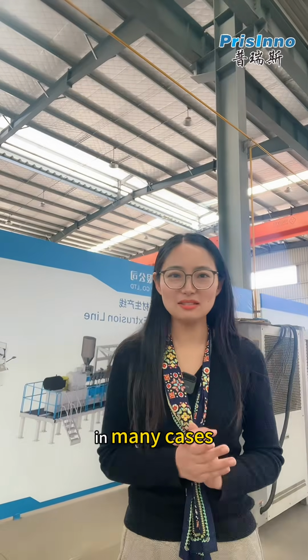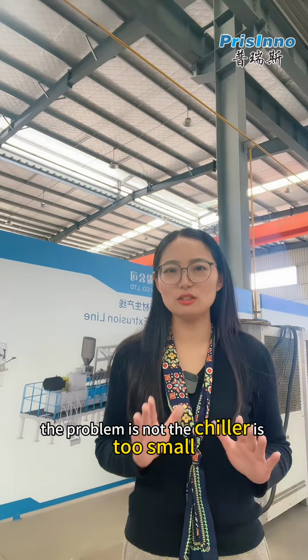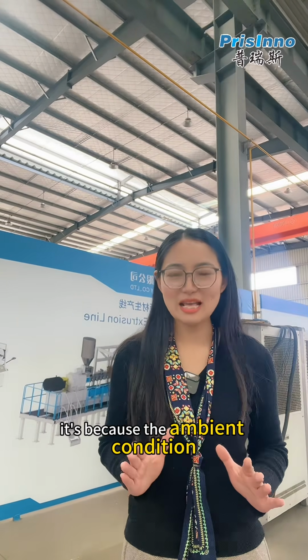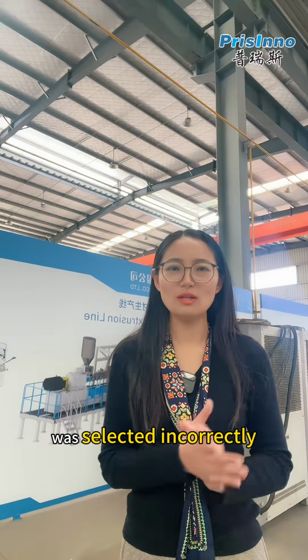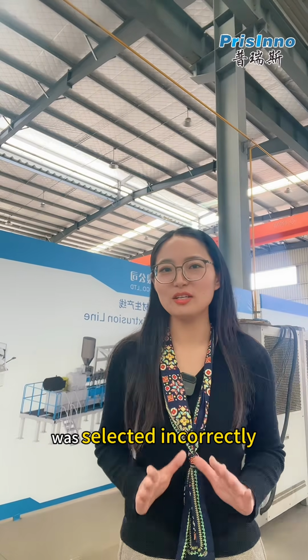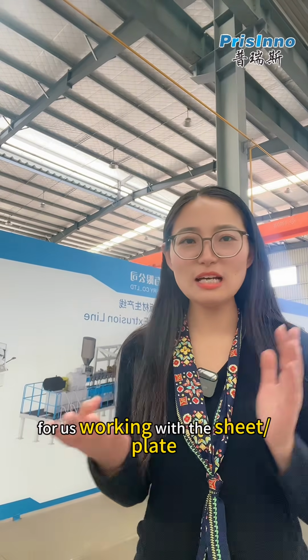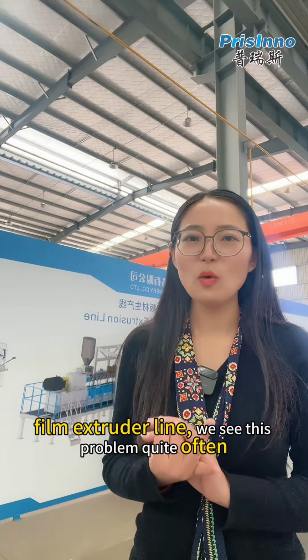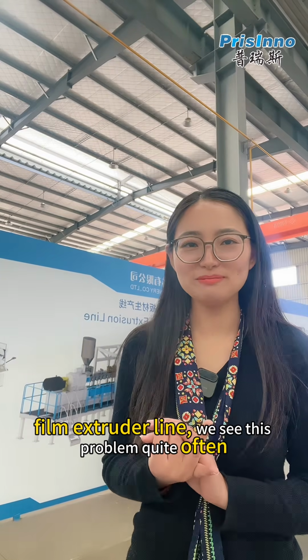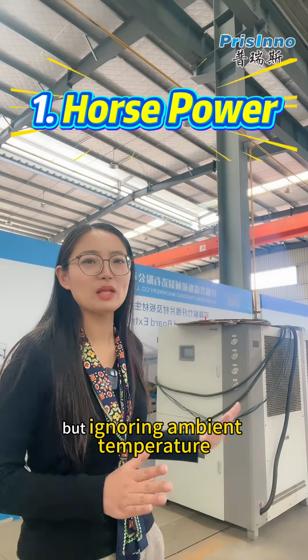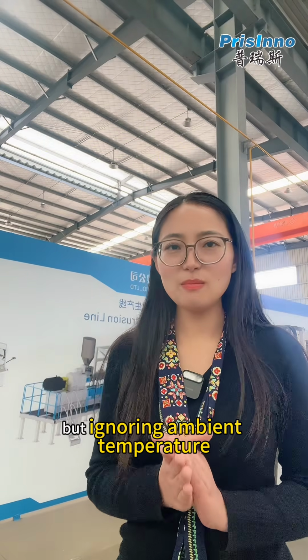Why does 60 horsepower still fail? In many cases, the problem is not that the chiller is too small. It's because the ambient condition was selected incorrectly. For us working with sheet and film extruding lines, we see this problem quite often. Many people choose the chiller by looking only at horsepower, but ignoring ambient temperature.